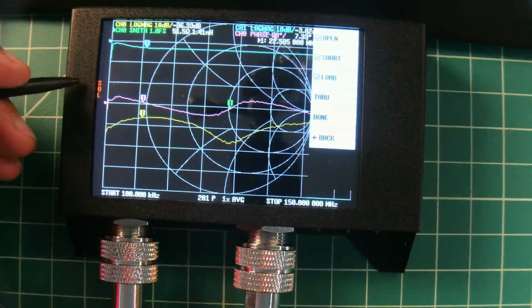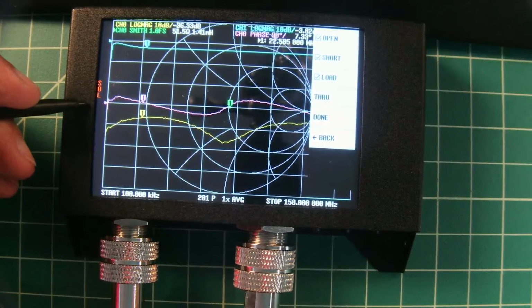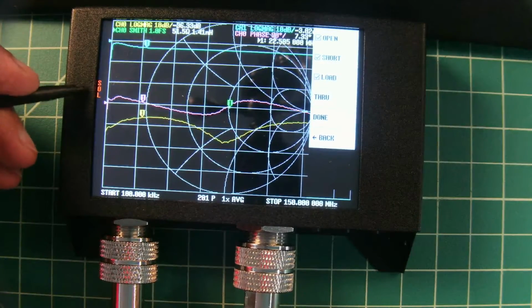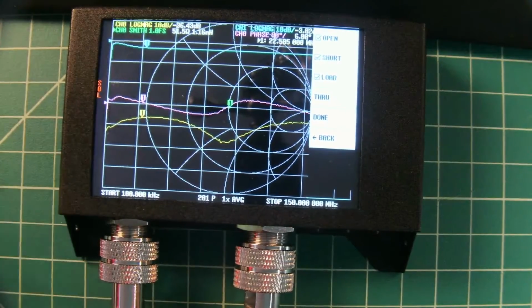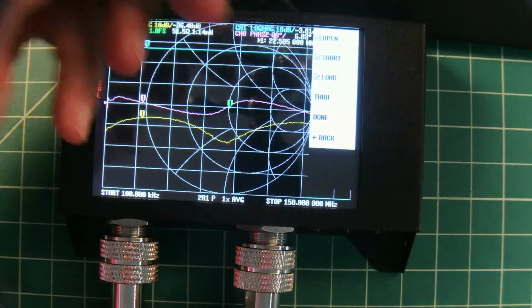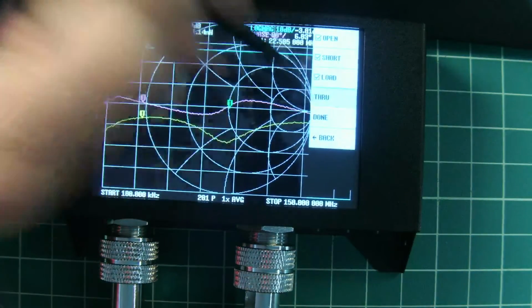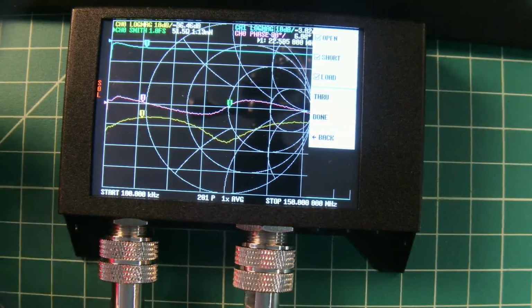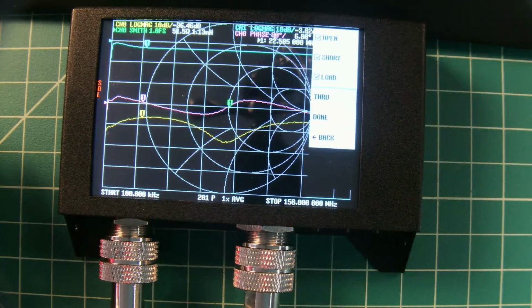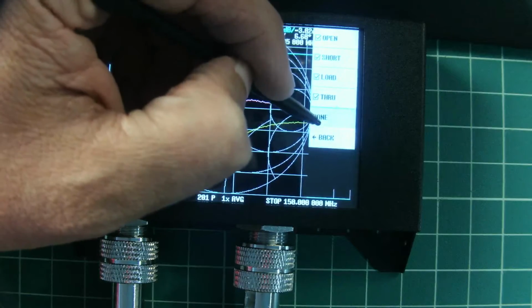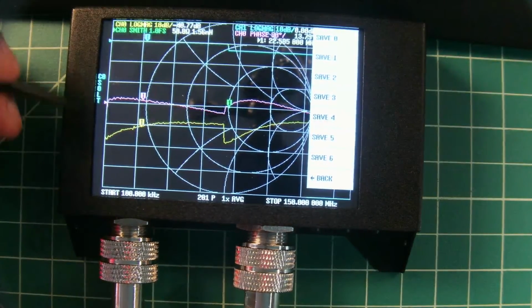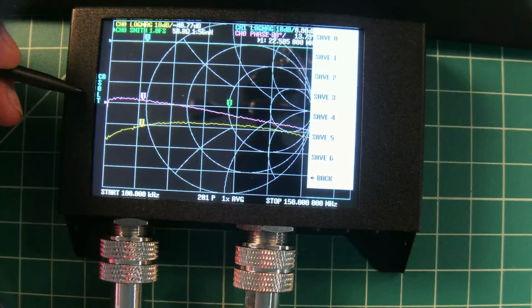You can see over here that certain things have happened. We have an SOL, and that is for short open load. And that means that those calibrations have been performed. They have not been saved, or we haven't hit that done button. These will change color once that happens. Let's go ahead and calibrate our through condition. And then I'm going to go ahead and hit done. And then you can see that we are good from a calibration setup.